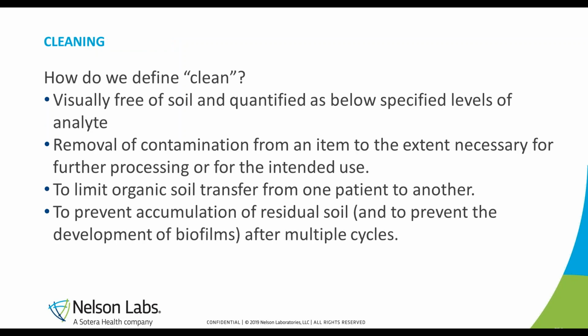Cleaning is perhaps the most important of all of these processing steps. The industry defines clean as visually free of soil and quantified as below specified levels of analytes. Cleaning is performed to remove contamination from an item to the extent necessary for further processing or for the intended use. This also includes allowing for successful subsequent sterilization steps, limiting to a minimum the organic soil transfer from one patient to another, and preventing accumulation of residual soils, such as preventing the development of a biofilm after multiple cycles.